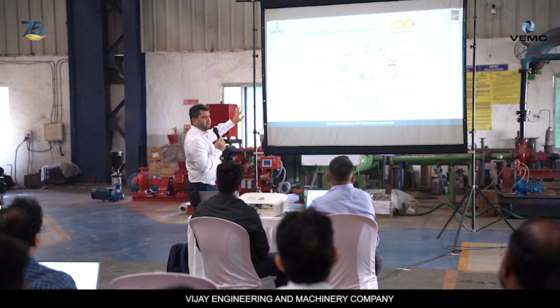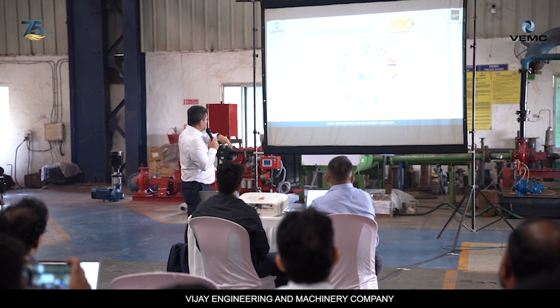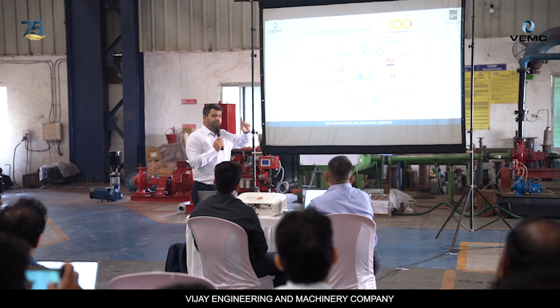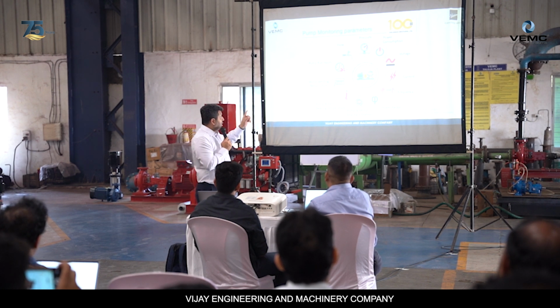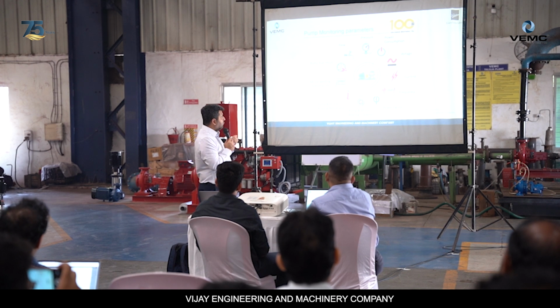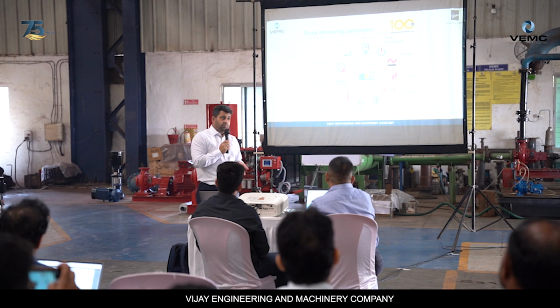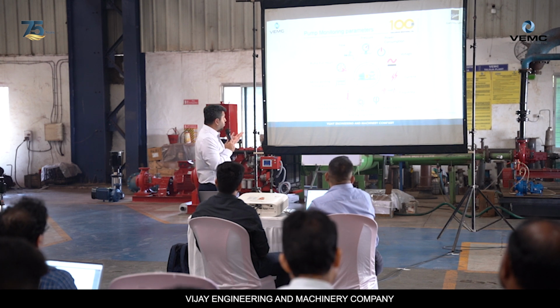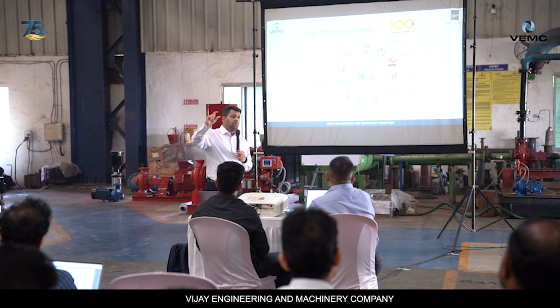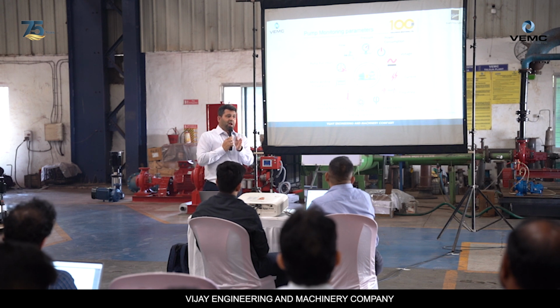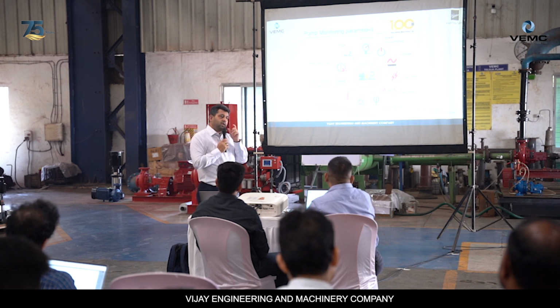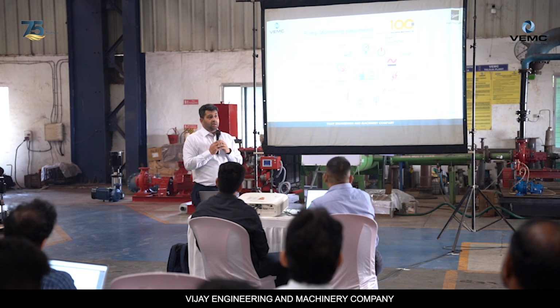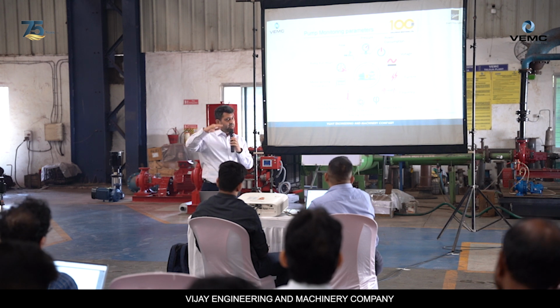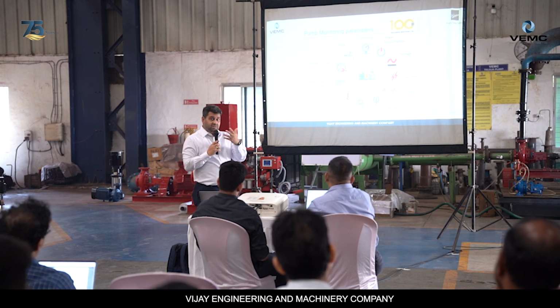These are your parameters - I'll go quickly so we can spend time on other things. So flow, pressure - but let me share with you, we need sensors put in. You have power consumption, voltage, what kind of current it's drawing, frequency, and power factor also plays a critical role. You have pump and motor bearing vibrations - a lot of the time alignments go out, so bearings are the first to go. But if you have a sensor in place, you could identify from the given limits that the bearing issue is there. Of course we send the data as per the data sheet, and from there we can really understand how this works.